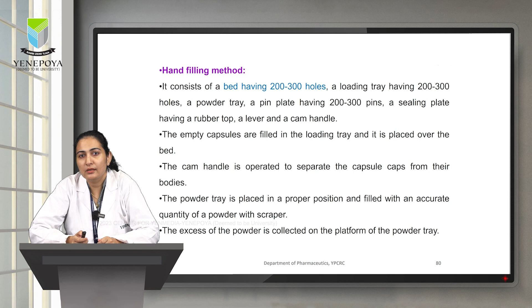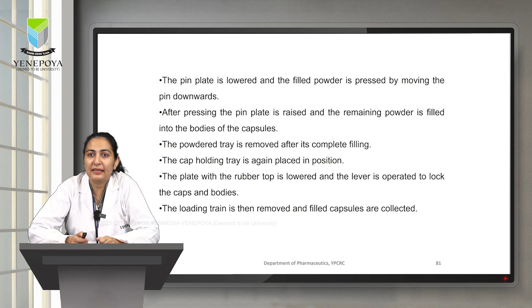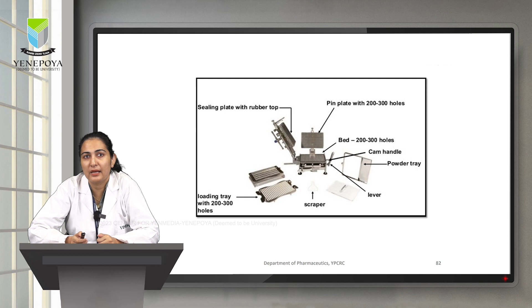The cap holding tray is again placed in position. The plate with the rubber top is lowered and the lever is operated to lock the caps in the bodies. The loading tray is then removed and filled capsules are collected. So you can see this is how we are going to fill the capsules with the help of this equipment. As you can see, there is a pin plate with 200 to 300 holes. The bed also comprises 200 to 300 holes. There is a cam handle, powder tray, a lever, scraper, loading tray with 200 to 300 holes, as well as a sealing plate with the rubber top.